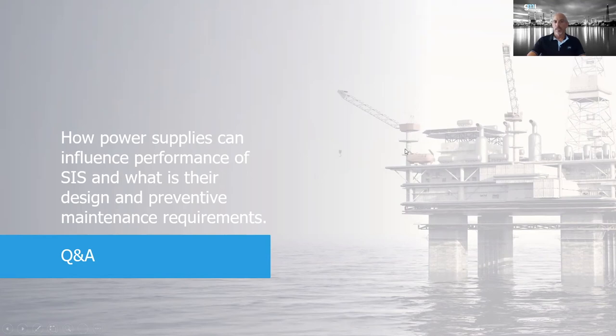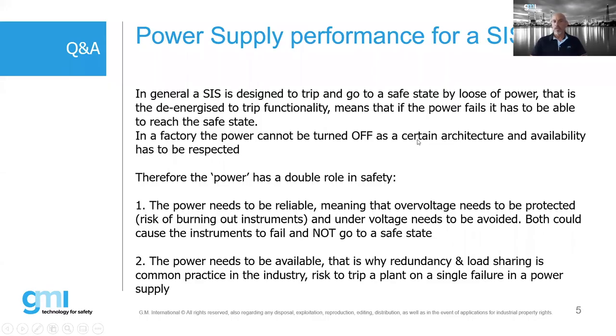We also say this point. In general, the power supply is designed to go to safe state by disconnecting power. So the de-energized to trip functionality is the safe state. But in the factory, the power cannot be turned off because of uncertain problems and so on. That is very critical. You cannot stop producing, maybe in a chemical plant and so on. And so they say that the power supply has a dual role in the safety.